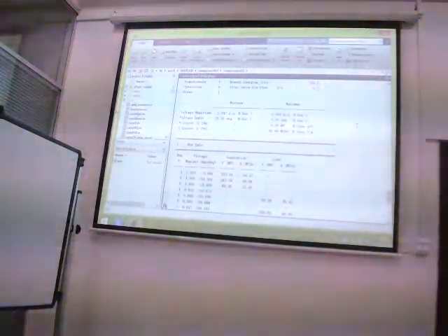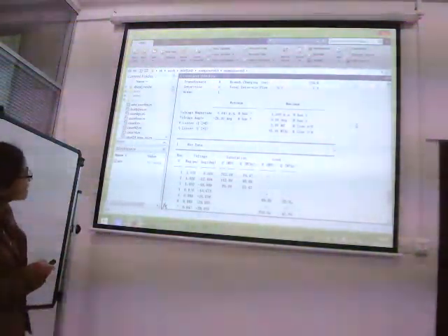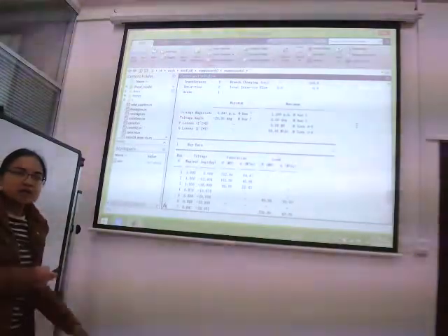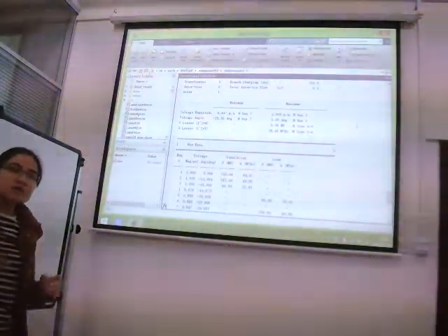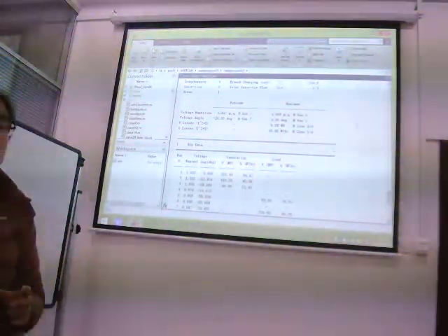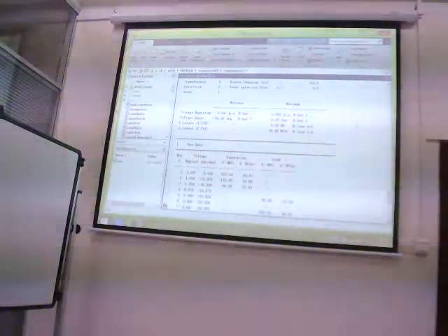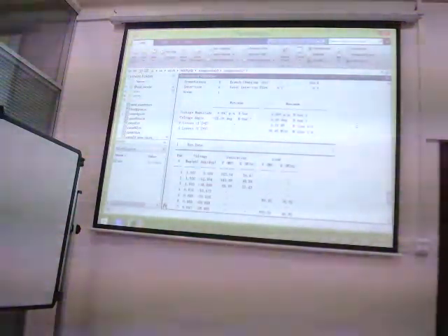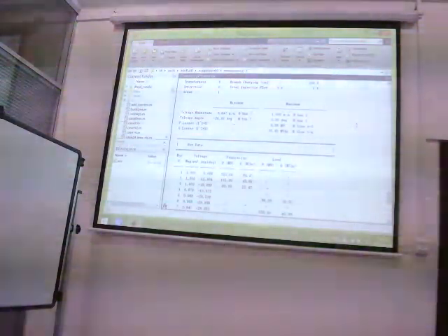Also, the voltage profiles change. The voltage value at bus 7 is the smallest one. It's below the given range, because for the given range the voltage value is 0.95 per unit. And the maximum value is still at bus 1, which is one per unit.